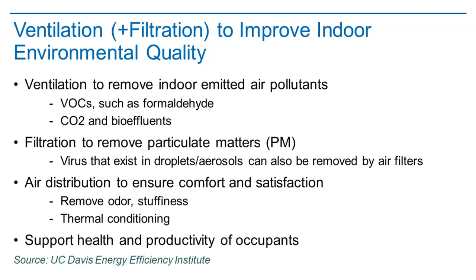Test and commission existing ventilation, like those schools in California, and install MERV 13 or better filters. But you can't just slide a new filter into any old HVAC—you need to make sure your HVAC is MERV filter capable. If it's not, consider portable air cleaners if they're not up to par, and note which systems are not capable, because that's a future retrofit opportunity.